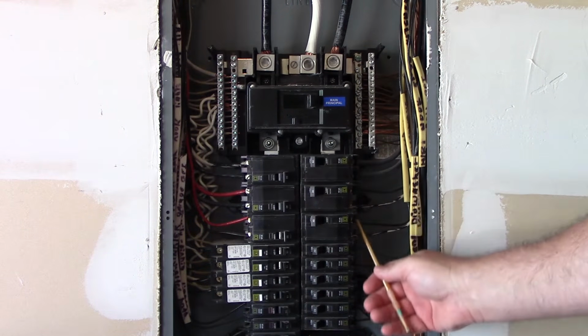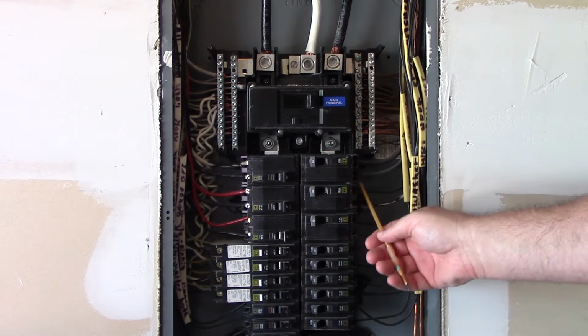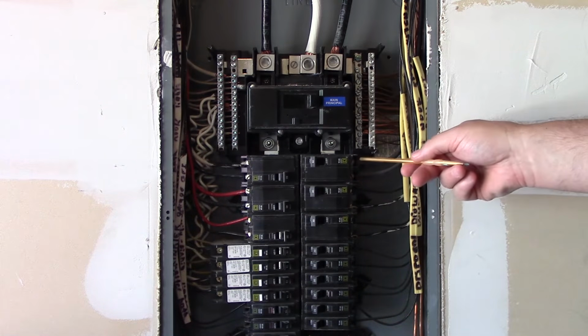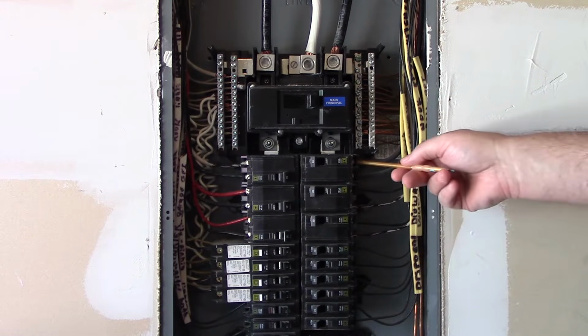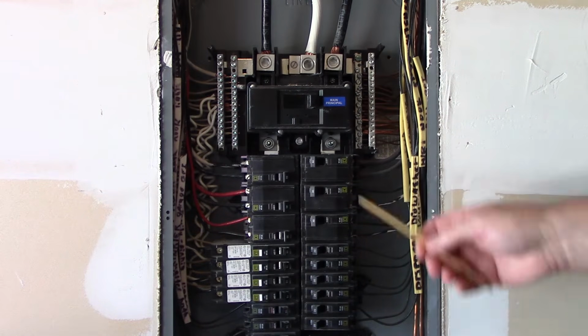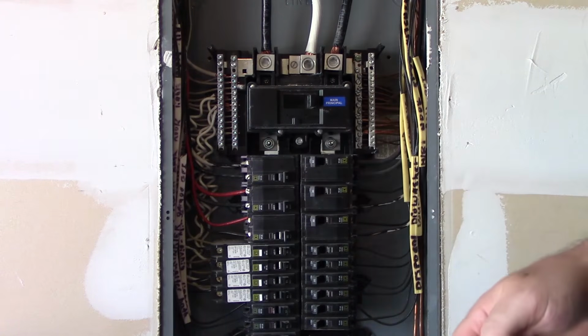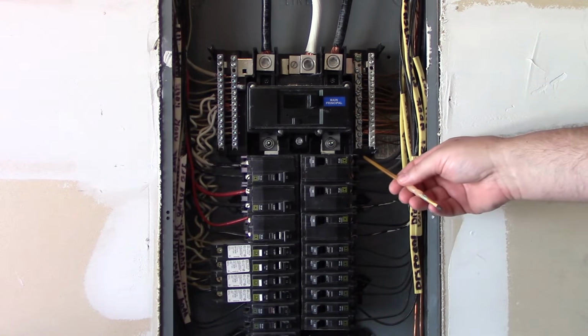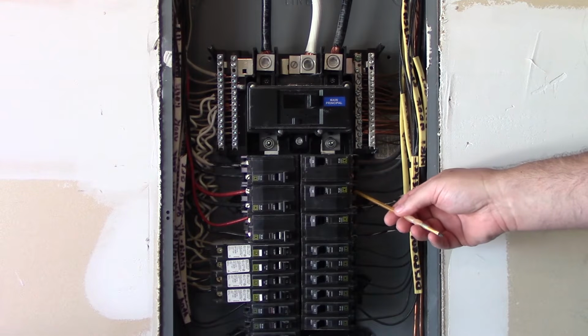Now, if these are aluminum conductors, there is absolutely nothing wrong with stranded aluminum. If I see some nicks on the copper or aluminum, I'm going to call that out, because a nick creates a resistance point in the actual wire, and we don't want that because it could generate heat. So we want to make sure that it's been stripped properly and it's terminating properly.